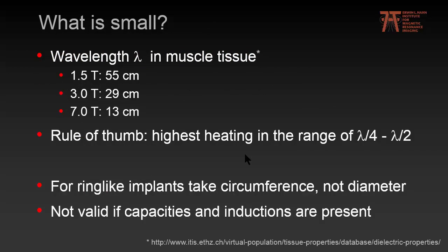What is meant with 'small' is of course with regard to the wavelength in human tissue. As field strength grows, the wavelength decreases, and as a rule of thumb, highest heating occurs in the range of quarter to half lambda. For ring-like implants, you should take the circumference, not the diameter. And if any capacitances or inductances are present, this could create a perfectly resonant micro-coil, making the simple size rule no longer valid.